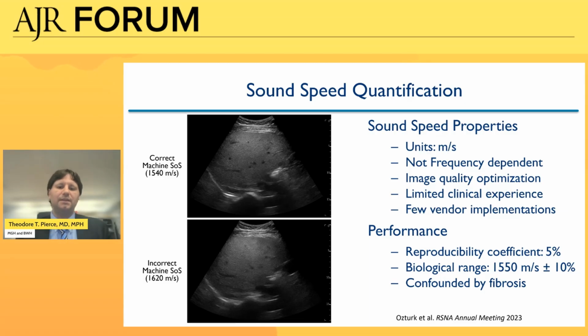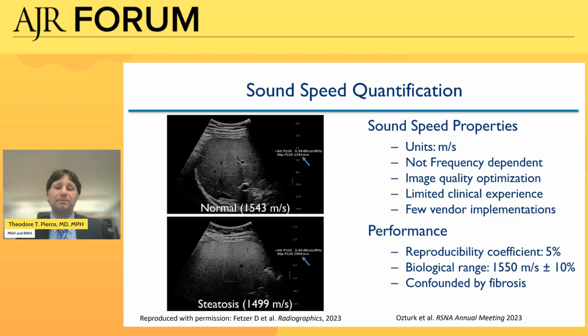On the top image, the sound speed is correctly matched to the liver, and the vessels are easily seen and defined, as you can see here. In the bottom image of the same liver taken at the same time, the sound speed that is used to reconstruct the image is incorrectly selected, and it leads to blurring of the vessels. Here's an example of the sound speed estimation tool, where the sound speed is estimated within a region of interest, and the value is reported on the image. As expected, the sound speed is slower in the fatty liver compared to the normal liver, which is shown on the top. However, there are several limitations to the clinical implementation of sound speed estimation.